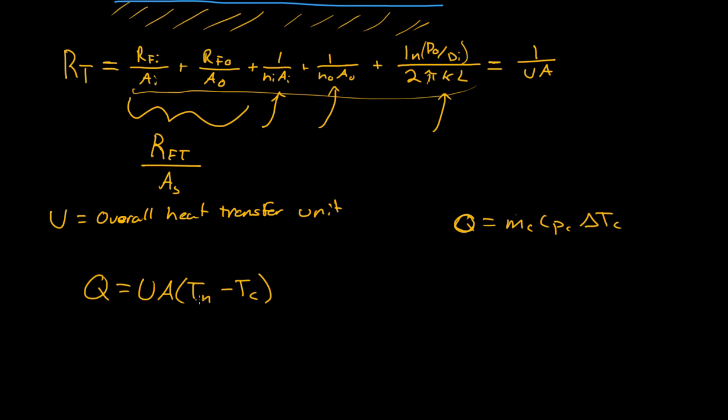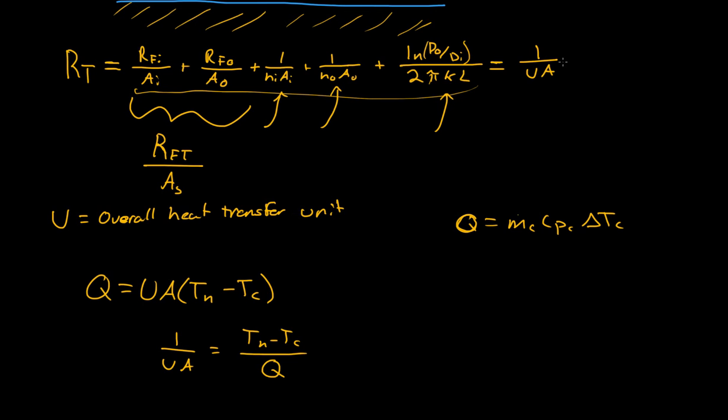If we have Q and we know what TH and TC are, we can get 1 over UA equals TH minus TC all over Q. So then we have what 1 over UA is. If we know what this is now, then we'll do a little bit of rearrangement and we can find what the fouling factors are. You can't find what these separate are, you can only find what their total is.